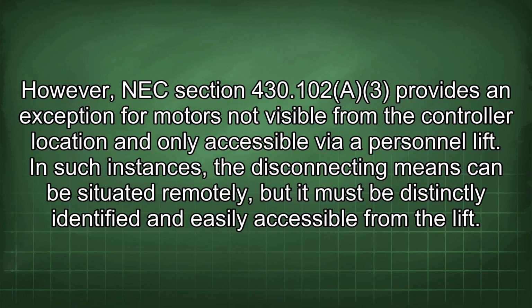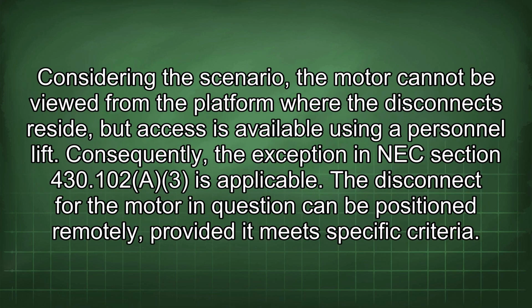However, NEC Section 430.102(A)(3) provides an exception for motors not visible from the controller location and only accessible via personnel lift. In such instances, the disconnecting means can be situated remotely, but it must be distinctly identified and easily accessible from the lift. Considering the scenario, the motor cannot be viewed from the platform where the disconnects reside, but access is available using a personnel lift.